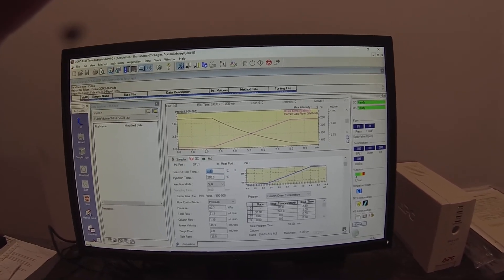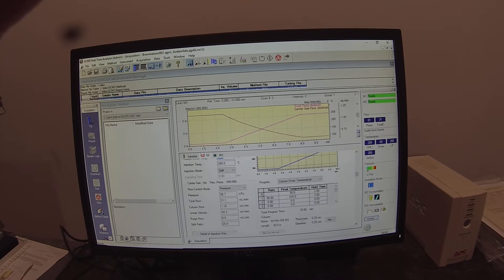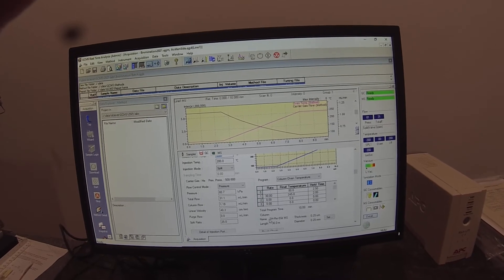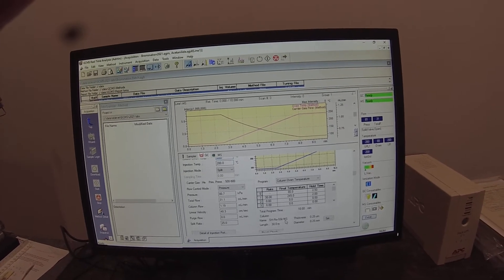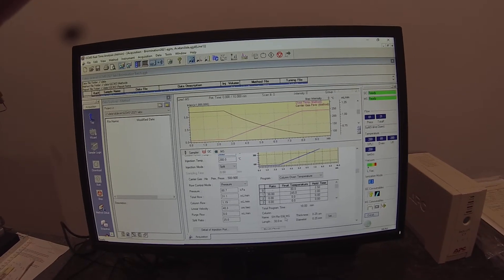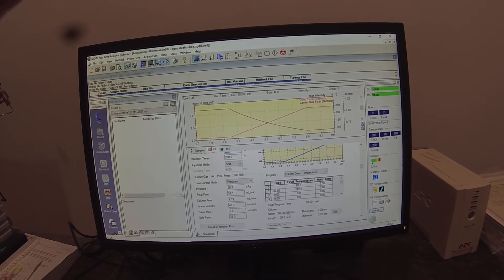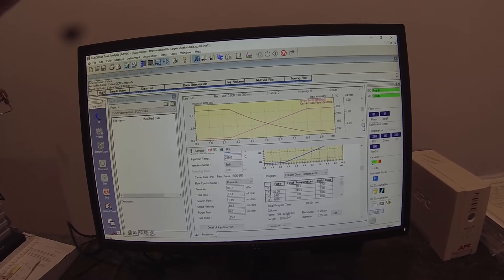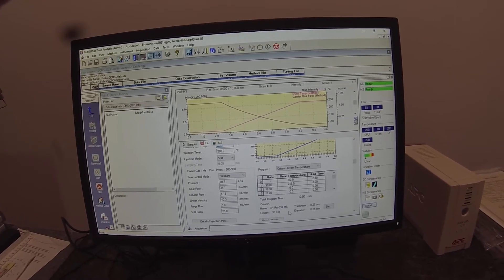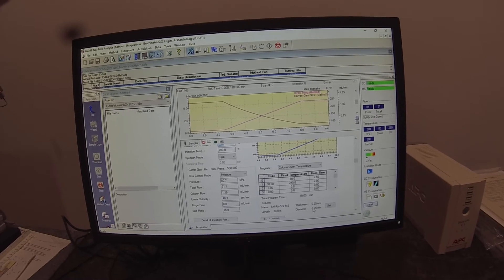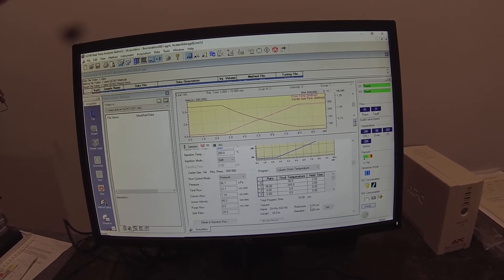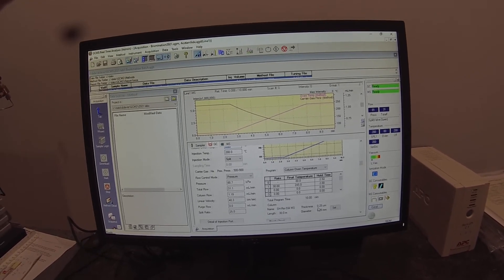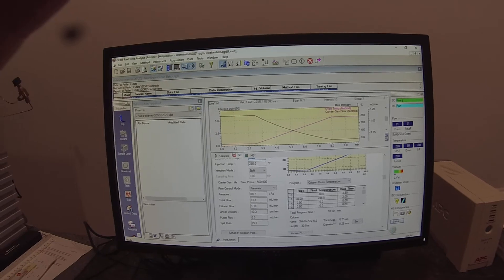We're using the same MS column we always do, that SH-RXI-5-SIL mass spec version, 5% diphenyl 95% dimethyl polysiloxane standard 30 meter by 0.25 millimeter diameter column with a 0.25 micrometer film thickness.